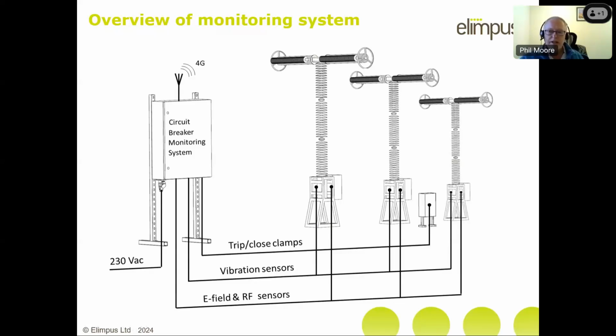In a circuit breaker that has a control switching relay, there will be 3 trip signals. We record that by putting a little clamp over the wiring. There's nothing invasive in any of this. It's no more invasive than opening the cabinet door anyway. We measure the close as well. In all the breakers I've looked at, the close has all been common, so there's only one of those. We measure vibration. The vibration gives you an idea of what the mechanism and the drivetrain is doing, and there's one fitted onto every phase of the circuit breaker. And then finally we measure both the electric field and the radio frequency emissions. These are normally done from the same sensor, and again they are bolted onto the side of the circuit breaker. In a GIS you would use the internal PD sensor to do this.